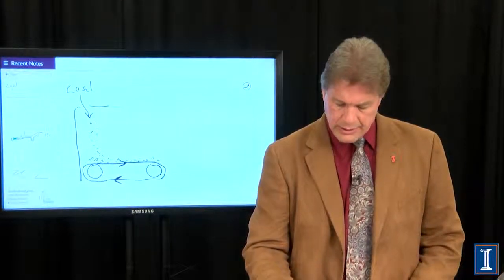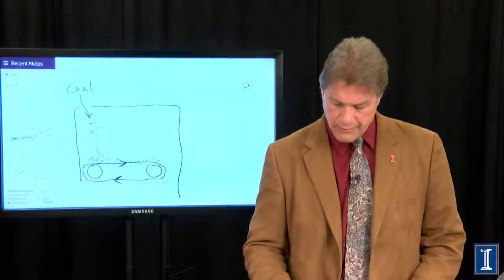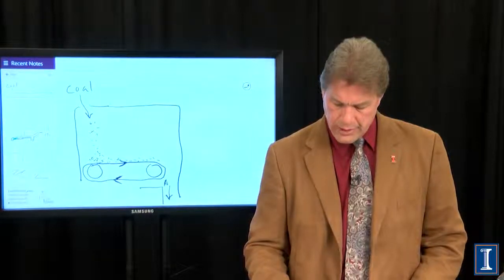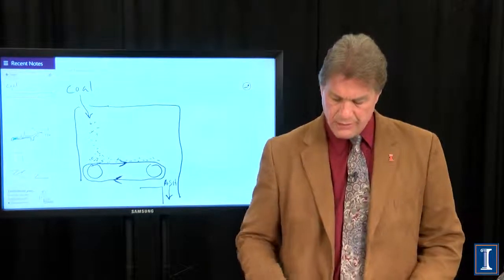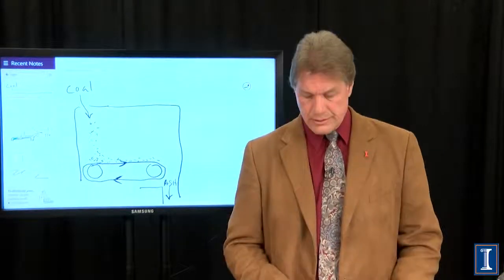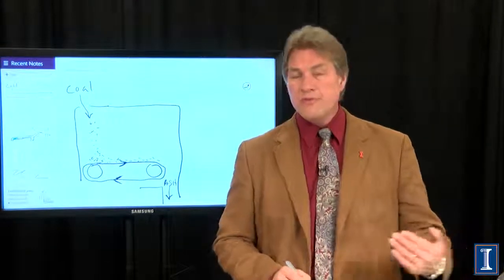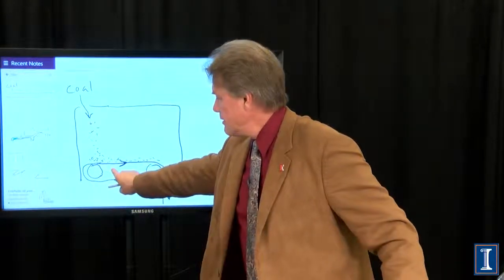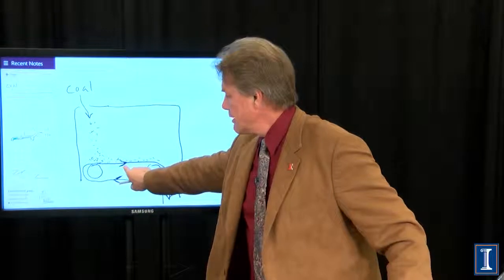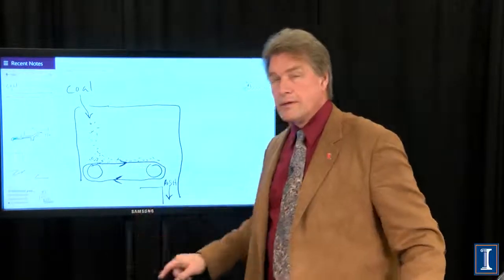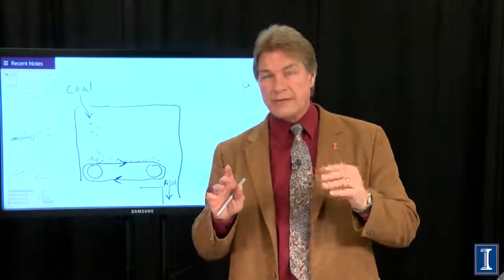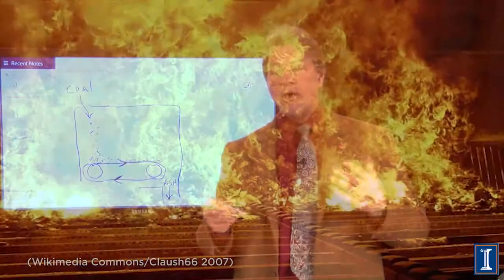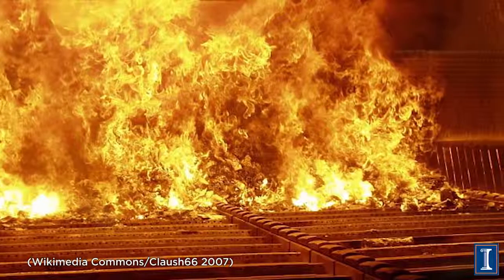The beauty of this system is that we have a gap here. And this gap allows the burnt coal, the ash, to fall off the end of the moving grate. And you time the movement of the grate. It's slow. But it's timed just right. So the amount of coal you're adding, by the time the coal gets to here, all of the energy content, ideally, has been spent.